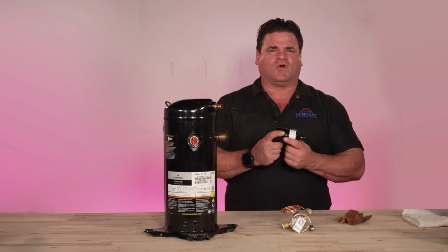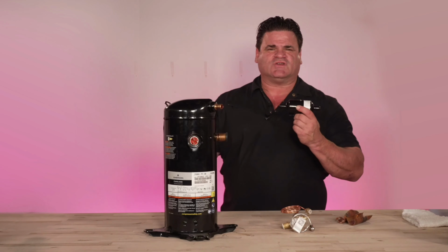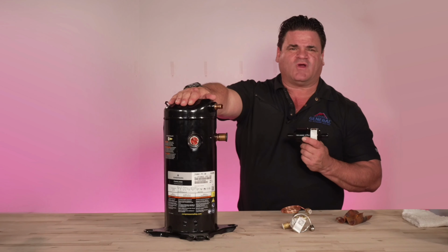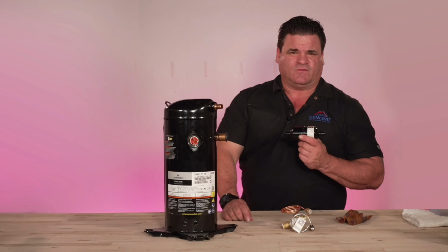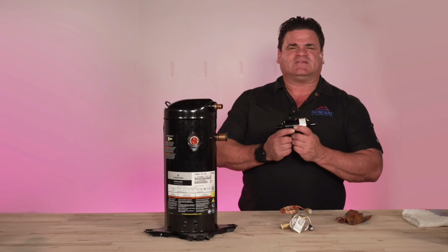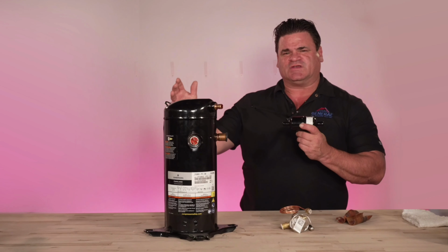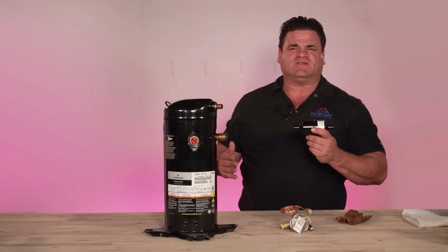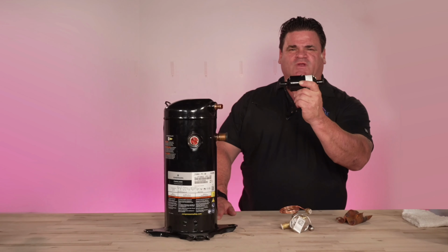The other thing that's really important to know, if you ever have to have your system worked on, if they've got to change a compressor, if they got to change service valves, which are on the condenser, if they got to change a TXV, if it has a leak that they repair, essentially, if they have to open up your system, the refrigerant loop, for any reason, this needs to be changed. That's how you reduce contaminants.